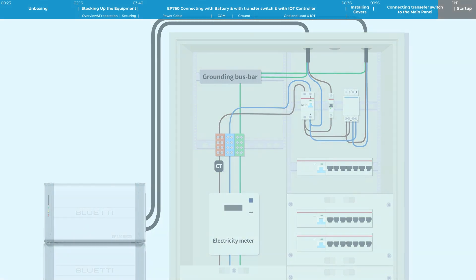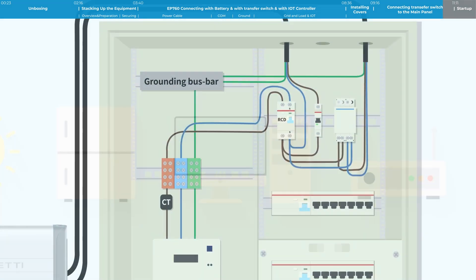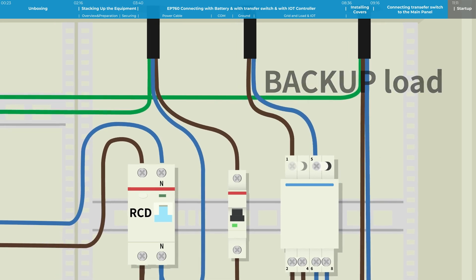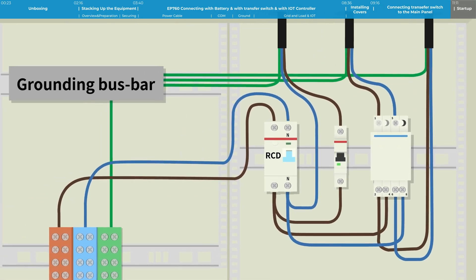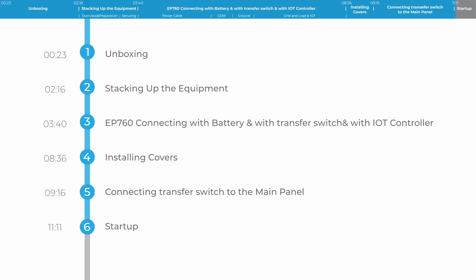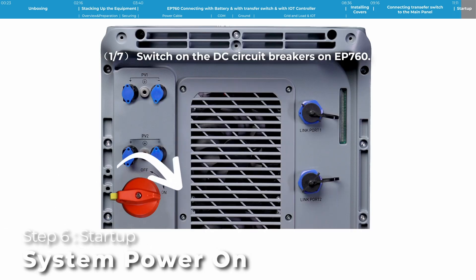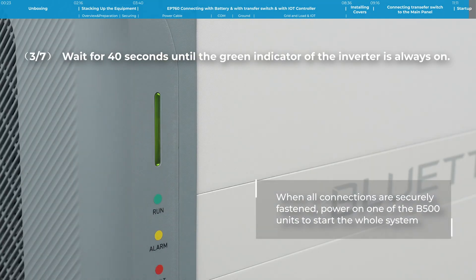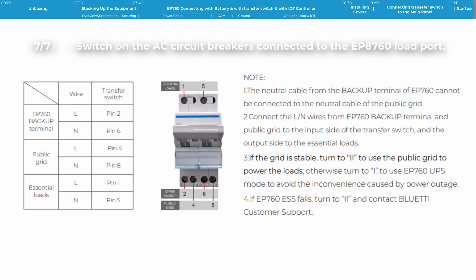Select some critical loads that need to operate during mains failure — e.g., lights, refrigerators, circuits supplying working computers or routers. Connect critical loads to the transfer switch: L to pin 1, N to pin 5. Please note that the total power of essential loads must be less than 7600W. That's all about connecting the EP760 to the home distribution box.